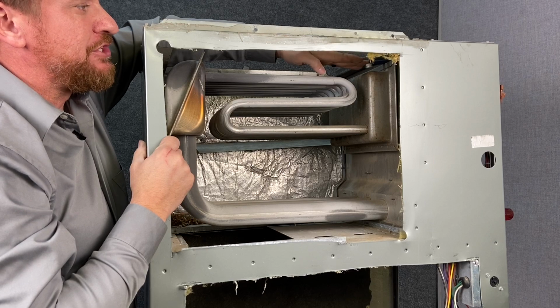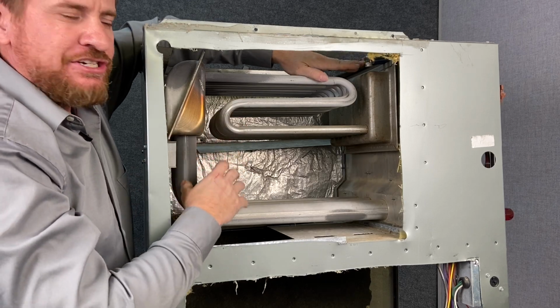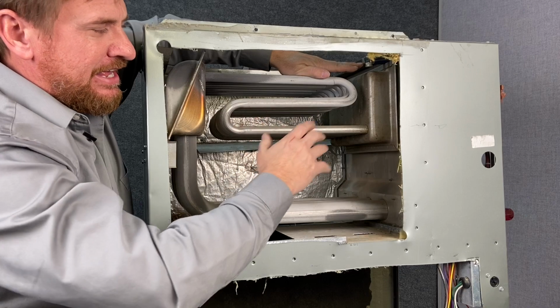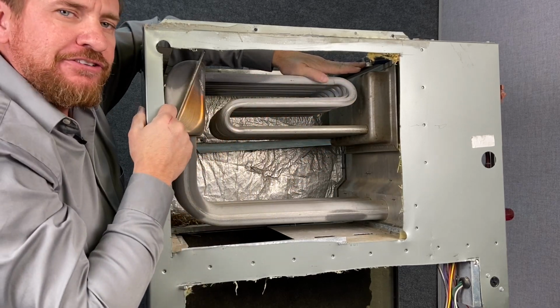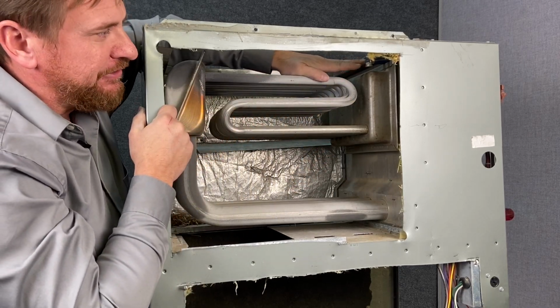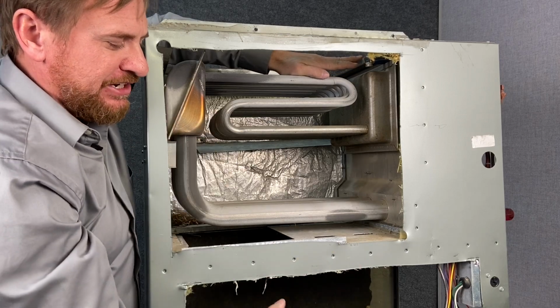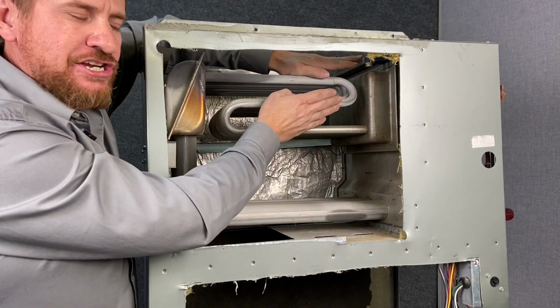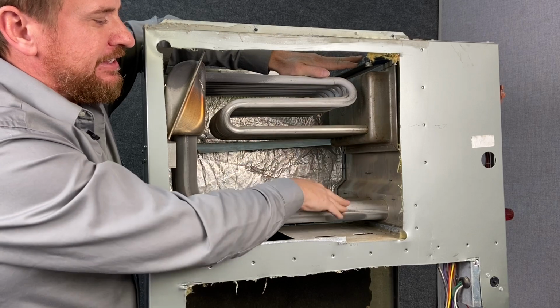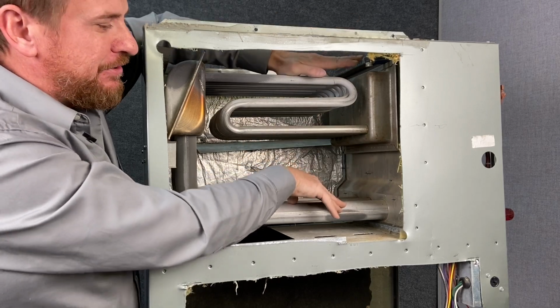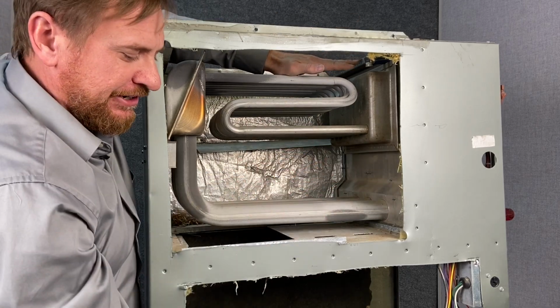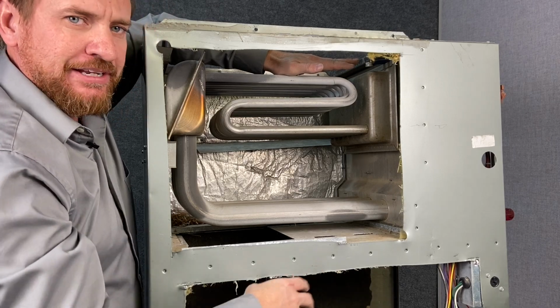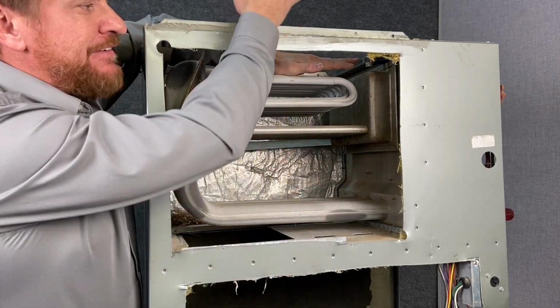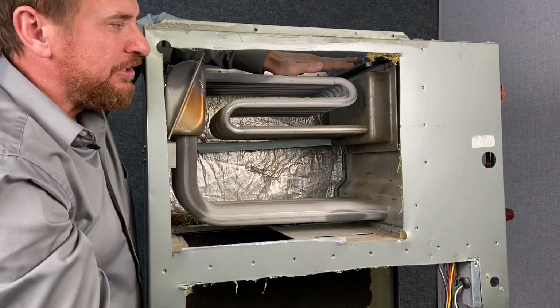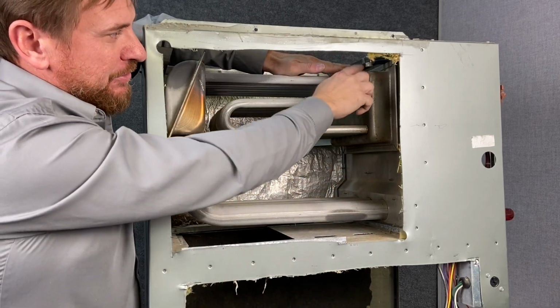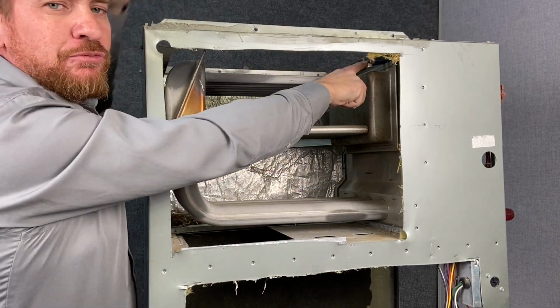If this limit switch opens, it shuts off the combination gas valve so that these don't get hot. If this limit trips, your first thought needs to be airflow, airflow, airflow. If this limit opens up, usually you're not getting enough air across the heat exchanger. A lot of new techs want to think that they need to have a problem with the gas pressure, and no, you need to be thinking airflow first. Dirty filter, blower not on the right speed, dirty blower wheel. Maybe the evaporator coil that's up here gets clogged up. All of these things, you're not getting enough air. So when this heat builds up, this limit switch will open.